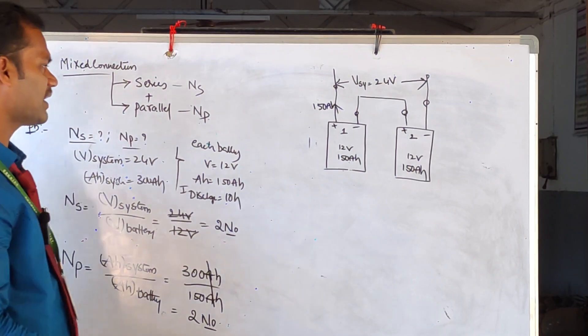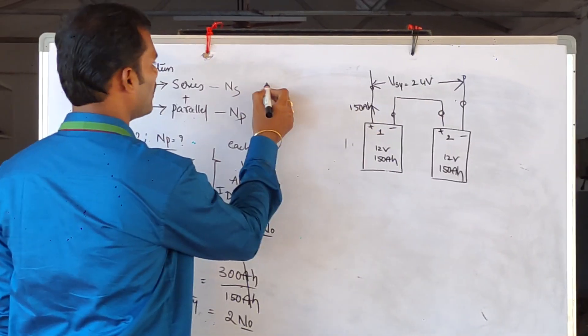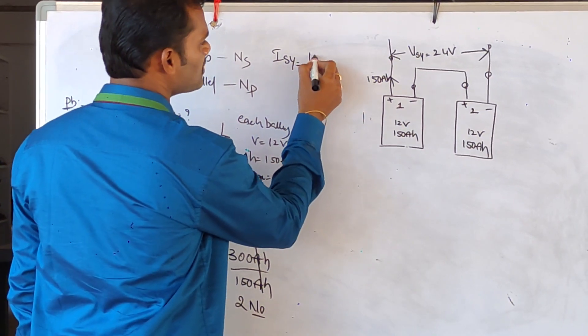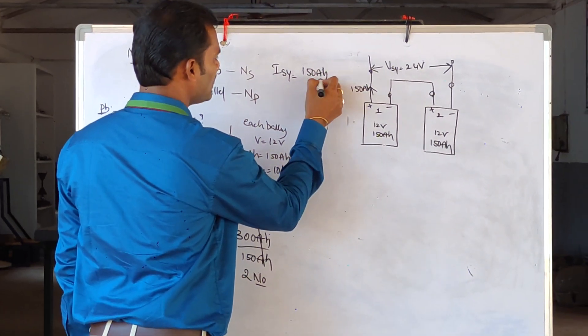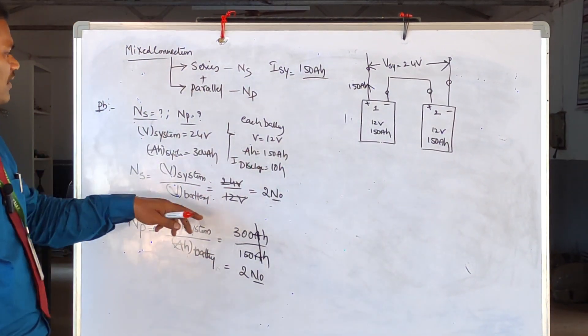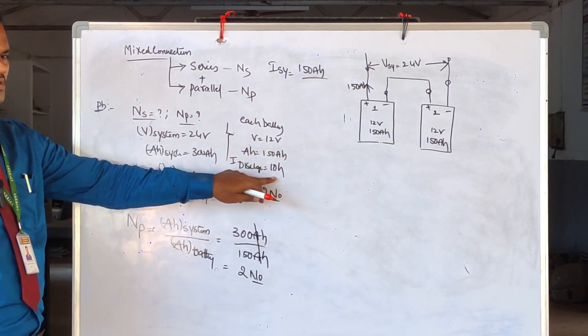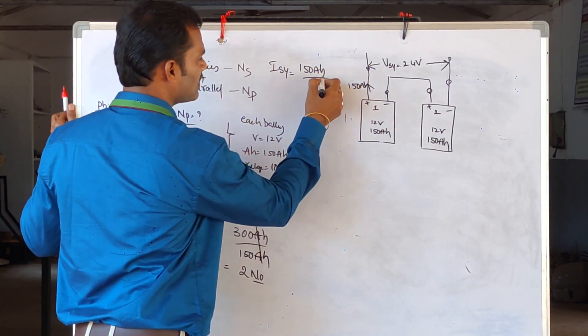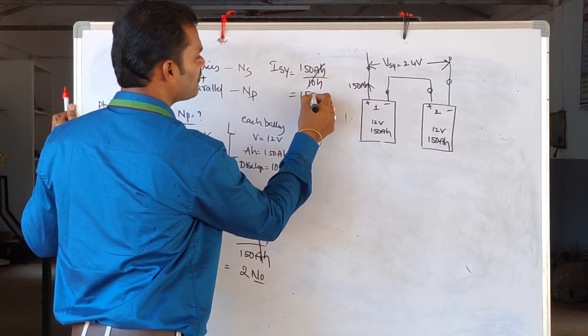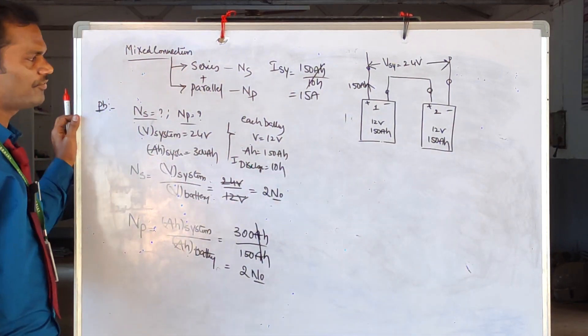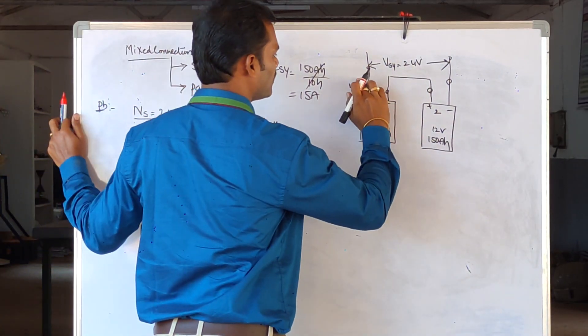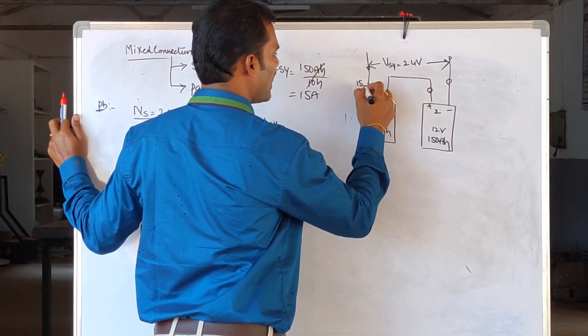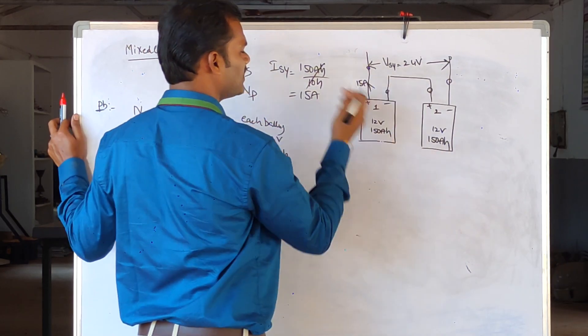To calculate the current from this series set: current equals AH capacity divided by time. That is 150 AH divided by 10 hours, which gives 15 Amperes. So each series set supplies 15 Amperes of current.